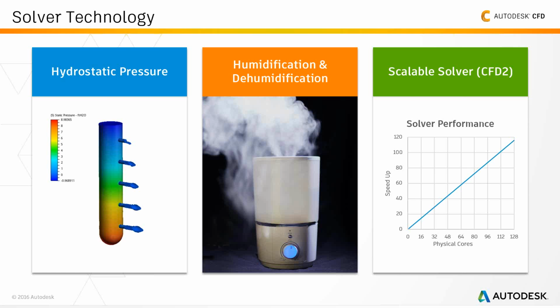Well, we added the ability for it to track scalar, which means humidity. It can track humidity now. And not only that, but we added the ability to specify how it could alter that humidity. So it could become a steam humidifier. It could become a regular dehumidifier, adiabatic humidification, and I think there's one more to go through the list when we show the live demonstration. But basically, anything you could do from a commercial humidification or dehumidification, it now has that capability as well.